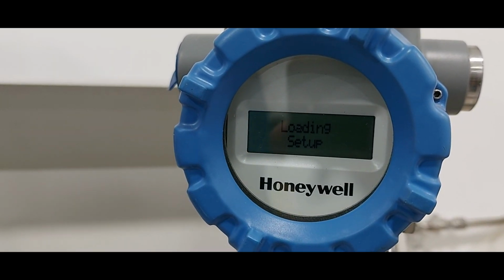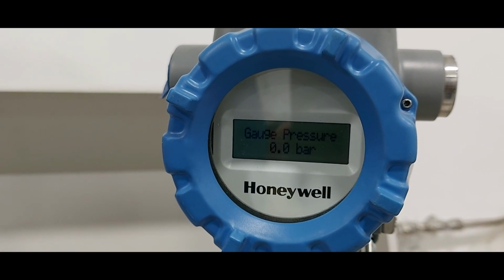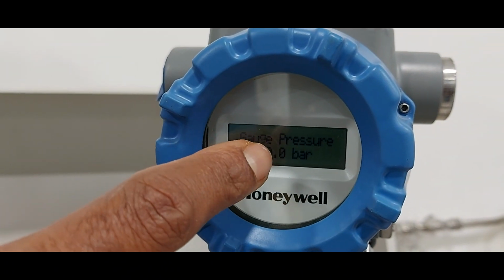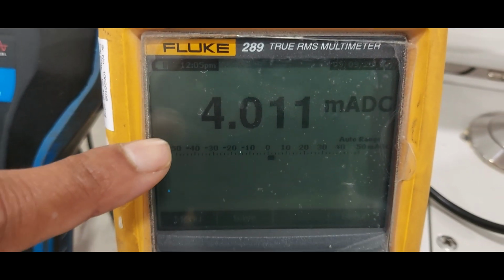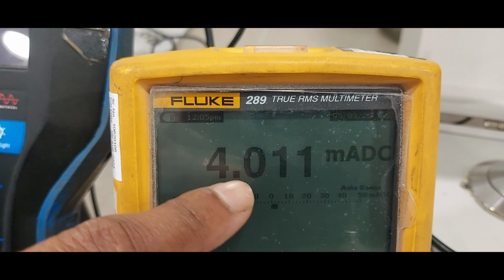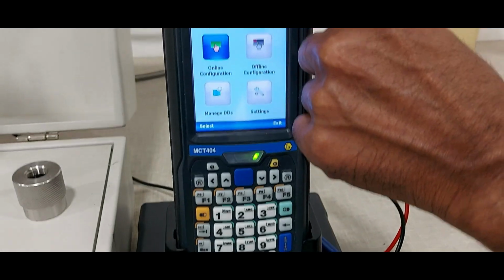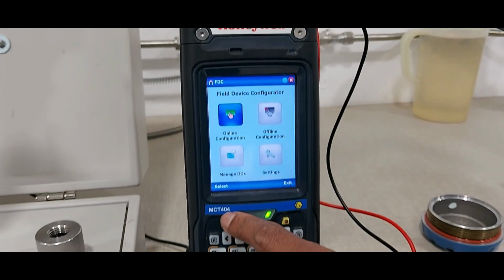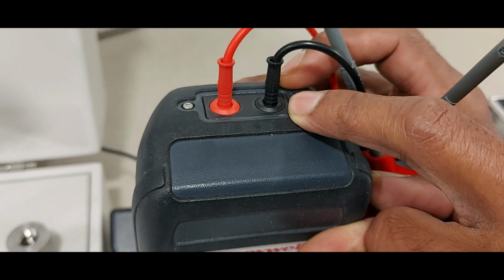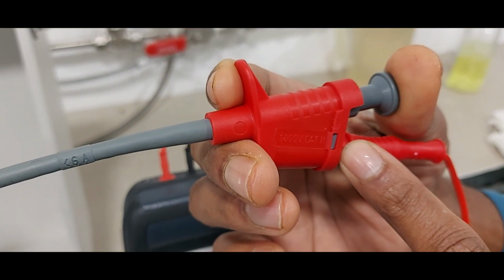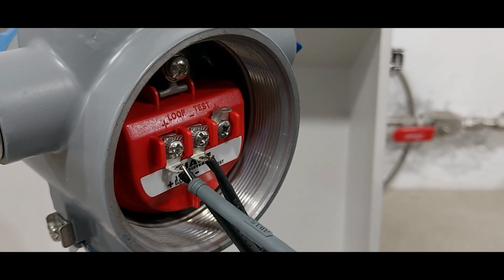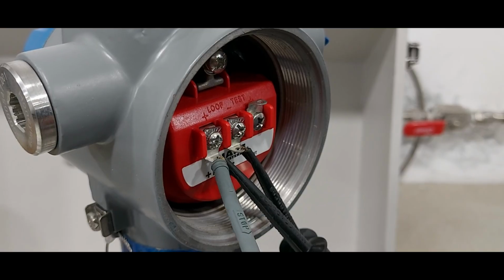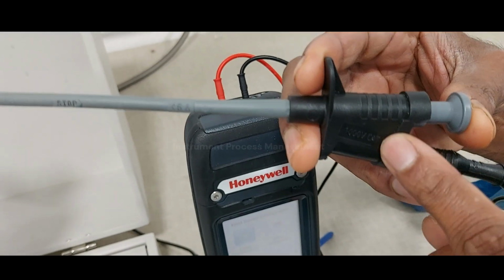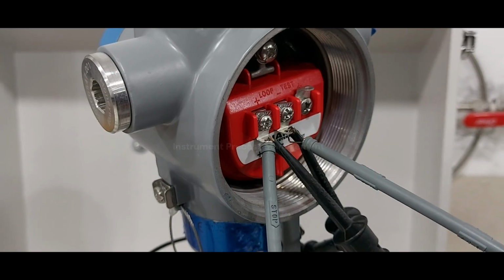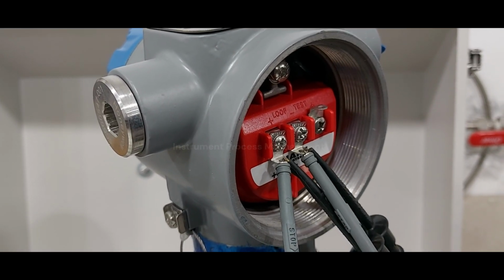Loading the setup. Gauge pressure showing 0.00. Transmitter output currently showing 4.011 milliamps. In the communicator, Honeywell MCT404, communicator positive lead to transmitter positive line area, negative lead connected to negative terminal area.